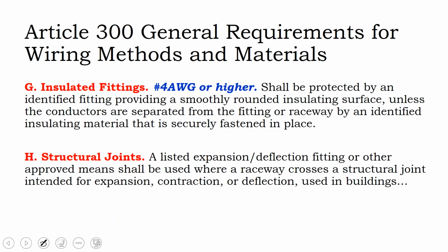Insulated fittings shall be protected by a smoothly rounded insulating surface unless the conductors are separated from the fitting or raceway by an identified insulating material that is secured and fastened in place. So this applies to number 4 AWG or higher. Let's say you have a 4-inch conduit and you want to shove a bunch of wires into it. You need to have a bushing around that smooths the edges, and you also may need a spacer to space the wires out from each other. So you may get a spacer inside that fitting as well. Not a bad idea to use on wires that are smaller than number 4. You don't want a rough surface on your conduit eating into your conduit cable anyway.